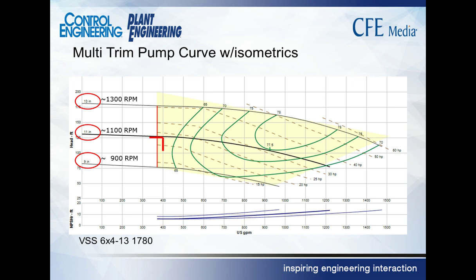In this case, I hope everyone can read the graph. We're looking for an operating point illustrated by the little upside down red L. We're looking for an operating point at 400 gallons per minute and 125 feet of head. And it should be evident that the efficiency on this operating point is not very good. While the best efficiency point for this pump is out there at 77.5%, we're operating well outside of even the preferred operating range and pretty close to the limit on the allowable operating range.